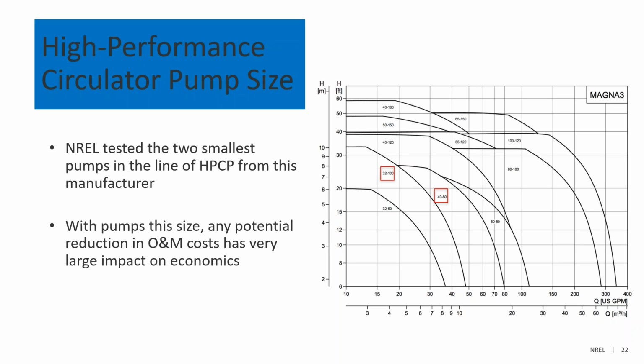When you're looking at things like domestic hot water recirculation pumps, normally you're going to have really high head pressure because you're having to pump that fluid up to the top of the building and then back down with relatively low flow rates. So where we were operating with these systems is over on the left-hand side where the 32100 is showing up, with high head pressure and low flow rates. One thing to note too is when we started the demo, the smallest pump they made was the 4080. And then about halfway through, they started selling the 32100. So we tested two different versions of this pump.